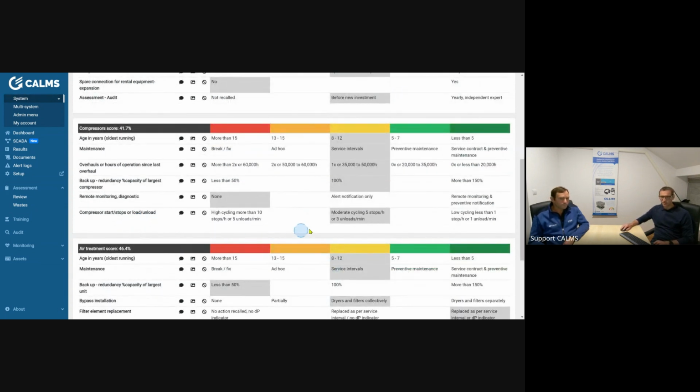From the old compressors, we see that one of the compressors is cycling quite often. It stops and starts and unloads a few times. That is quite funny, because I don't see that with the VSD. Maybe we need to buy another VSD instead. I know, of course, because this one is cycling. Yeah, you're right. The VSDs don't cycle. I love them.